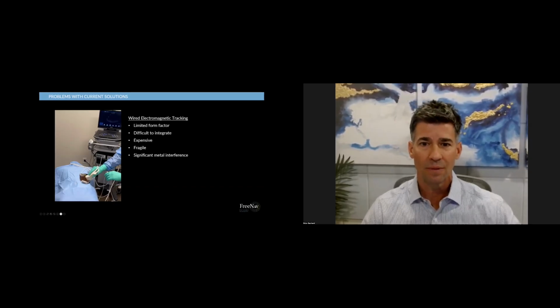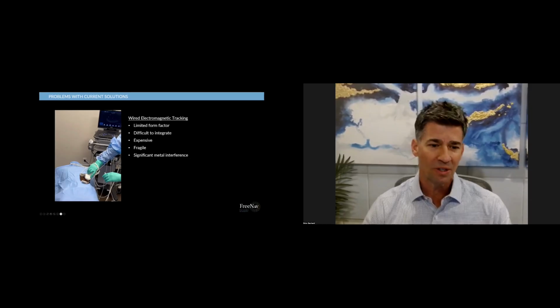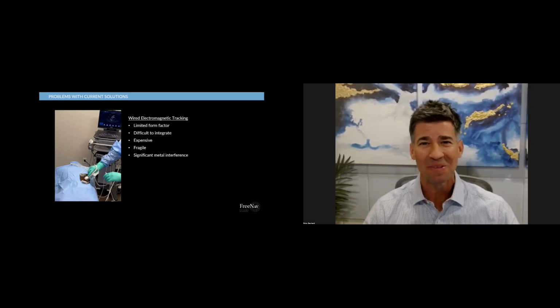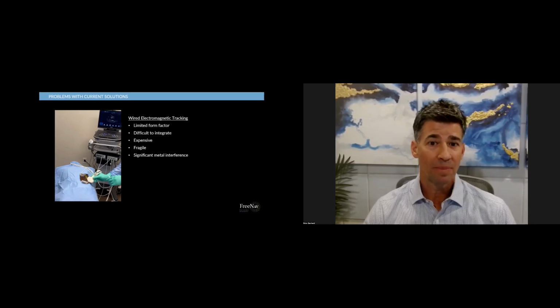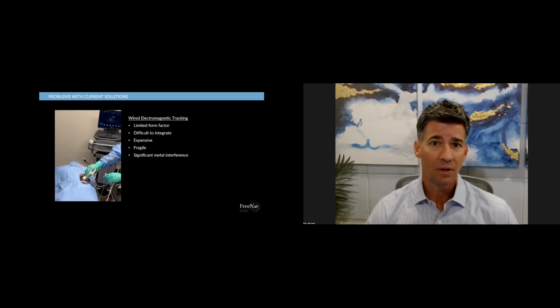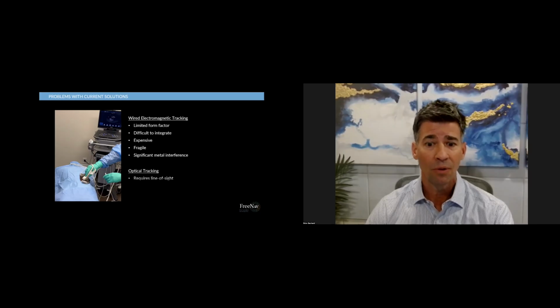With the current wired electromagnetic tracking, unfortunately, this isn't actually a human on the table, so I'll point that out. But there's a challenge with the form factor of it being wired. It's difficult to integrate these wired sensors. They're expensive, often fragile. They break during manufacture. And the number one thing we're hearing from our partners and customers today is the significant metal interference that is a result of having those wired sensors in the field.